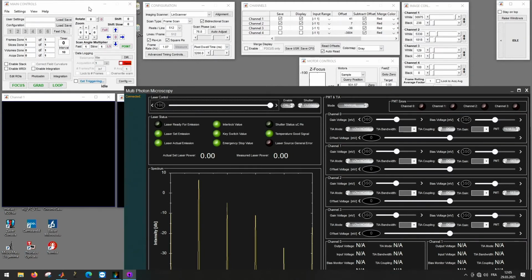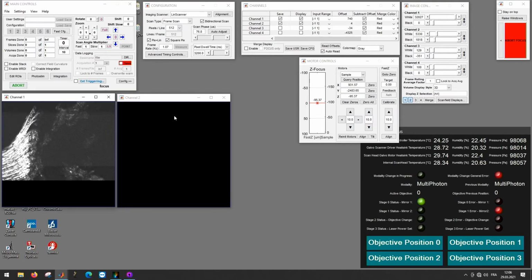I think most of you that are working with scanning microscopy are very familiar with the scanning software. All the parameters are already set for finding the focus or realigning the position for your region of interest. I always choose a little bit lower resolution than 512, but of course for the image itself we will increase the resolution. Right now we have a dwell time of 0.2 microseconds per pixel, which is convenient for most of the imaging.